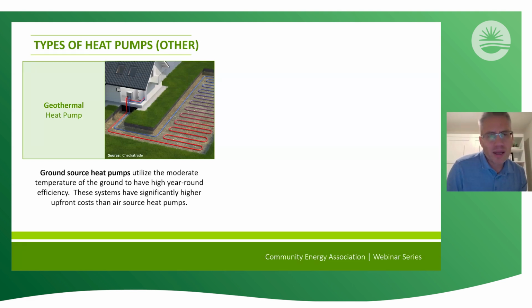And then, a less common heat pump system is ground source heat pumps. This utilizes the moderate temperature of the ground to have a high year-round efficiency. And these can be ground source or ocean source or lake source geothermal systems. And these have a significantly higher upfront cost than your air source heat pump. So you typically see them utilized more so in estates or commercial applications. Would you say so, Rob? Is that fair?